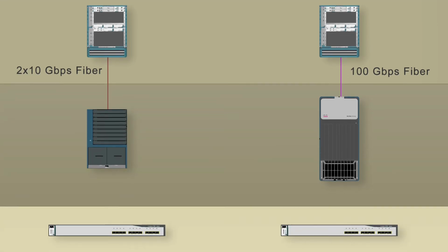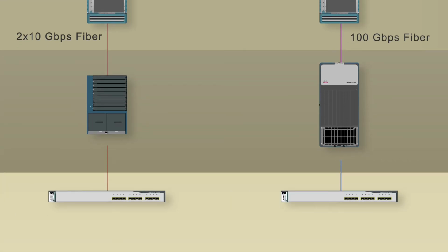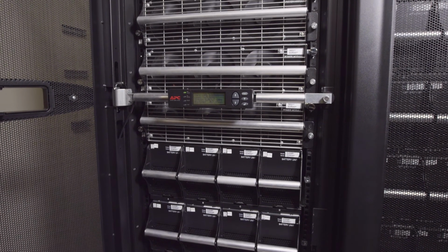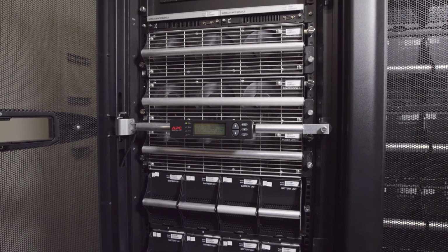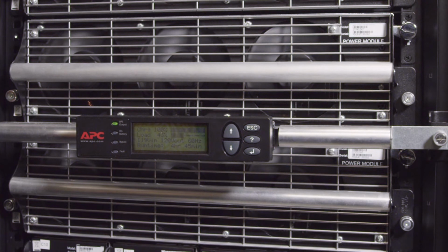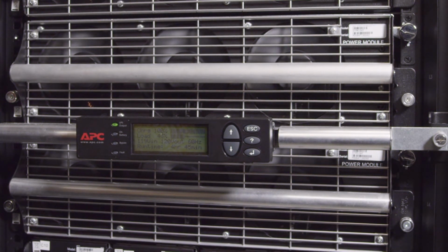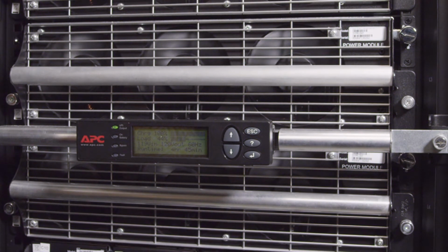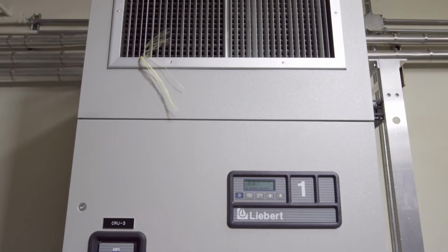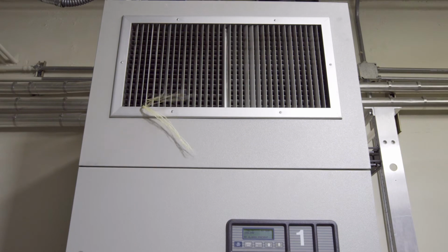These links also use the same single-mode fiber that we use from the buildings to the distribution nodes. All devices we use at USF's distribution layer have redundant power supplies and, where possible, redundant forwarding hardware. The node itself has a dedicated generator, and UPS capable of running the room for at least 4 hours in the event of a power failure, including if the generator doesn't start, and sufficient redundant cooling to keep the room at around 72 degrees even if all but one of the air conditioning units fail.